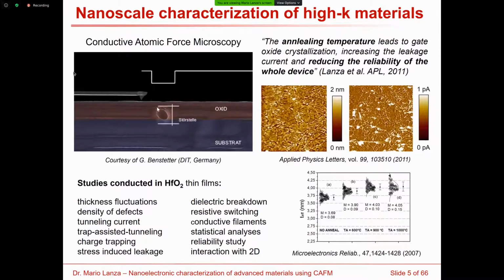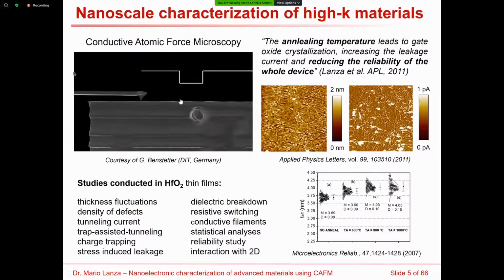And then if you can scan the surface of the sample and move the tip from one line to another, you can make a three-dimensional map of the electrical conductivity of the sample that you're going to study. And at the same time, because it is based on atomic force microscopy, you can also construct a topographic map. And these two images are constructed simultaneously, but at the same time independently.